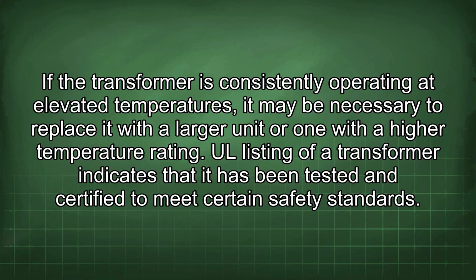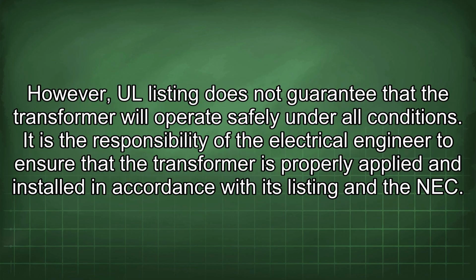UL listing of a transformer indicates that it has been tested and certified to meet certain safety standards. However, UL listing does not guarantee that the transformer will operate safely under all conditions. It is the responsibility of the electrical engineer to ensure that the transformer is properly applied and installed in accordance with its listing and the NEC.